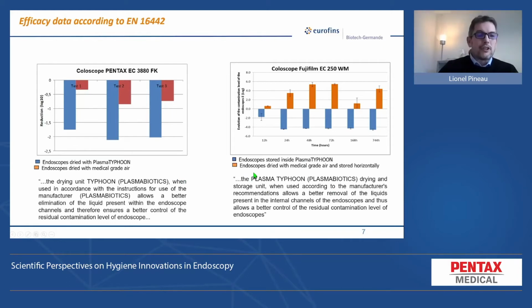And definitely this result confirms that the drying unit Typhoon, of course, when it's used in accordance with the instructions for use of the manufacturer, allows a better elimination of the liquid present within the endoscope channel and therefore ensures a better control of the residual contamination of the endoscope.